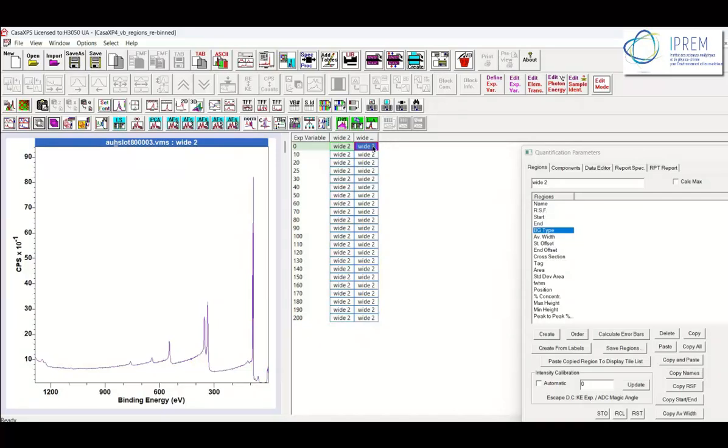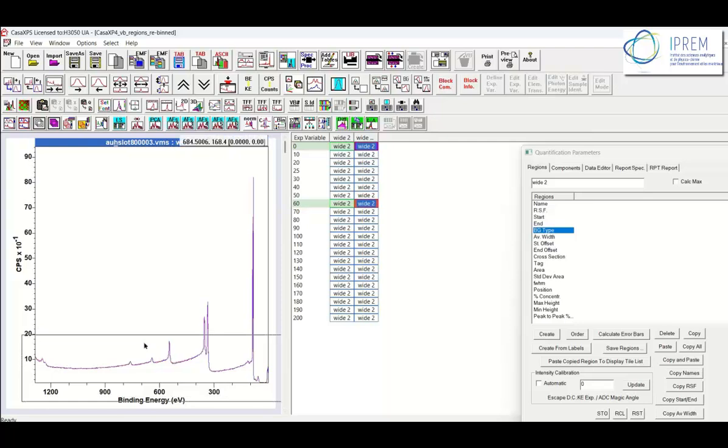Okay, so this is my reference spectrum, and this is what it looks like calculated with a transmission corrected calculation that I've just performed. So there we can see there are some differences here, a little bit of differences, not too surprising. If I start using arrow keys and start stepping up, you can see that as I get into the range of data that was used to do the calculation, I'm getting pretty close to what the NPL data looks like.